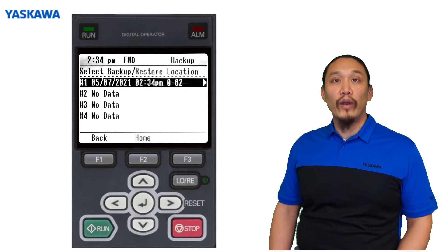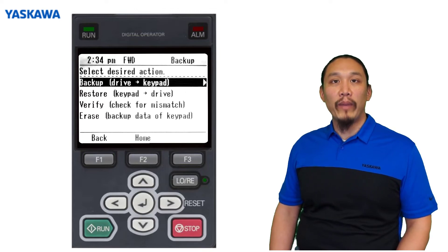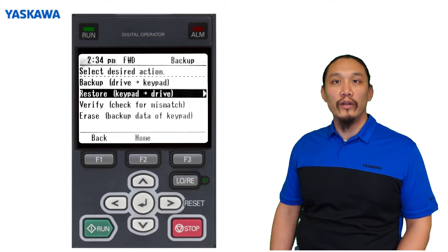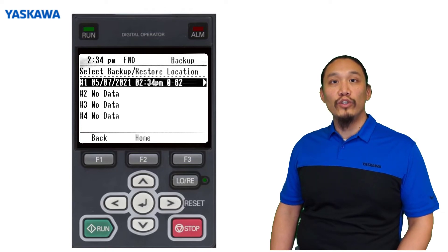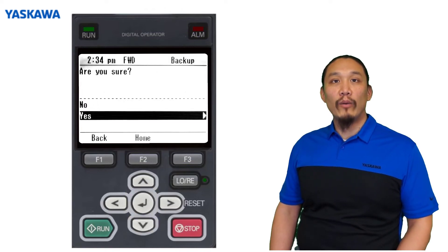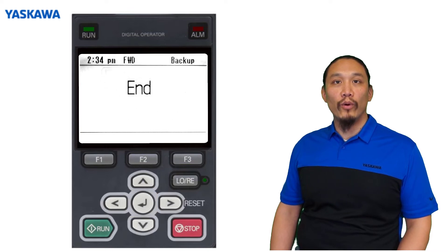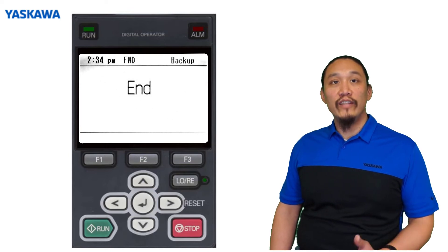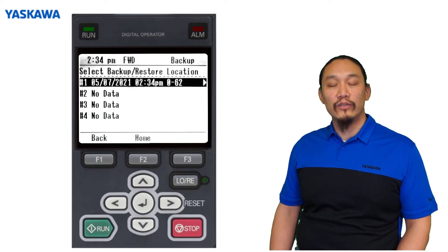To restore the parameters to the drive, navigate to the backup/restore menu and select restore. Select the backup you want to restore to the drive and press enter. The drive keypad will write the parameters to the drive control board. You have now restored the parameters.